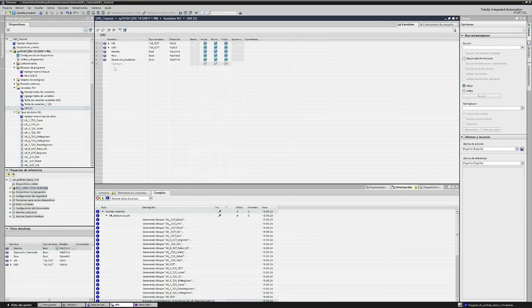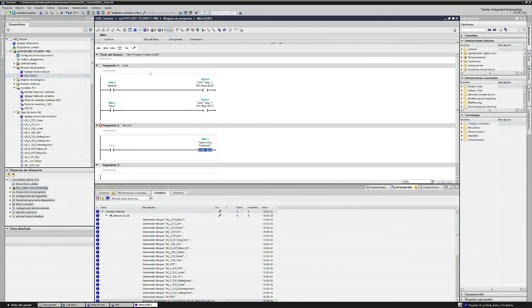It's good practice to use memory addresses instead of outputs. After adding all of this, we will change into memory addresses. This way, you can use them in different function blocks and you won't be limited by the number of outputs or inputs you have. You can create any amount of memory addresses — as long as your PLC can handle it.